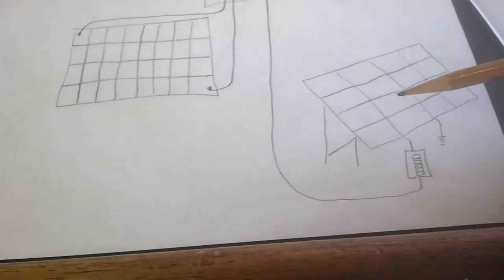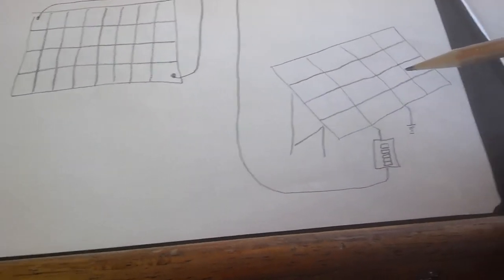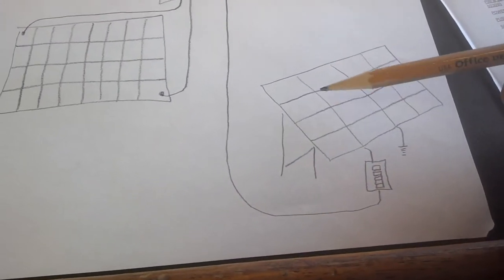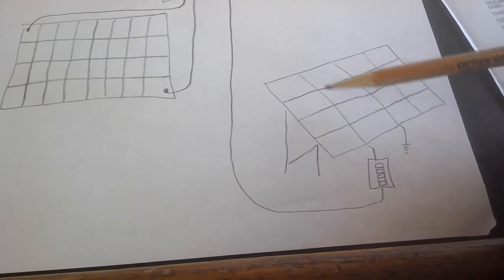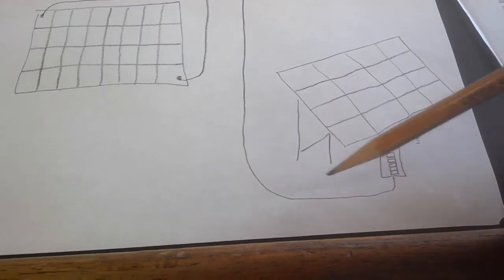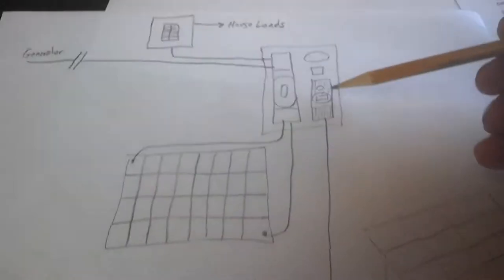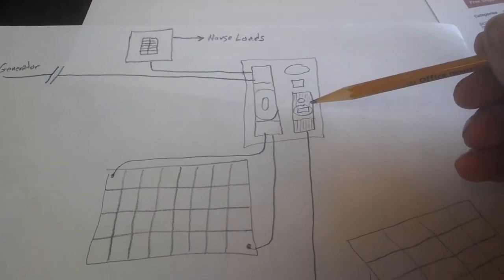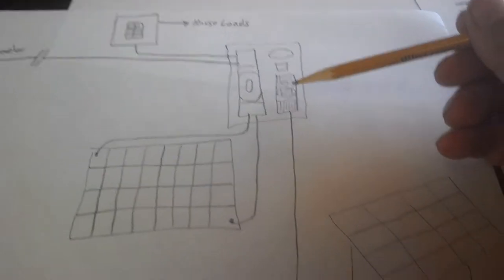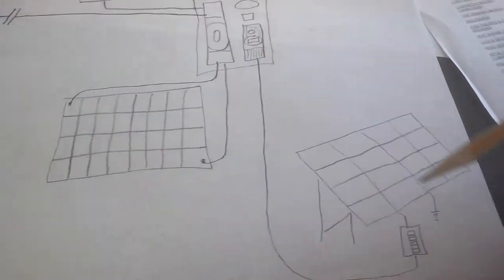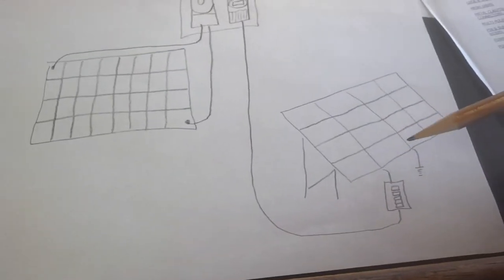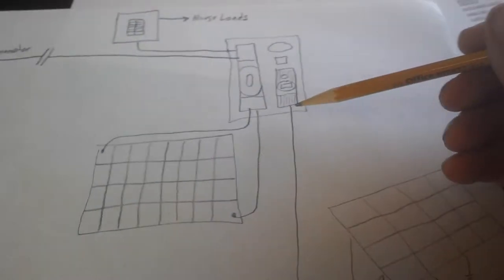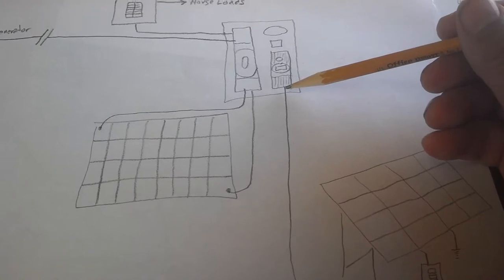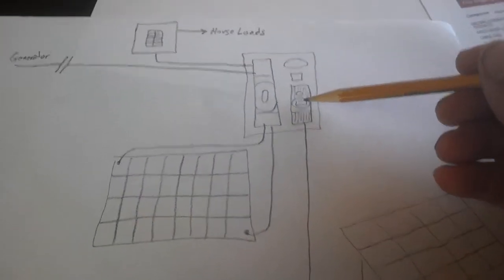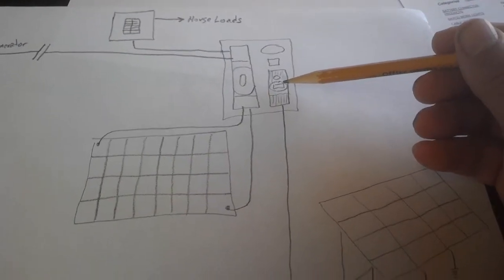And at the maximum rating for the panels, wiring three panels in series should be pumping about 105 volts into this. The charge controller will take a max of 150 volts, and we leave a little room for temperature compensation and different spikes and that sort of stuff. But anyway, at the maximum amperage at 100 feet, if we keep it under 100 feet, we'll experience between 2 and 3% voltage loss by the time we got here, which I think is acceptable.